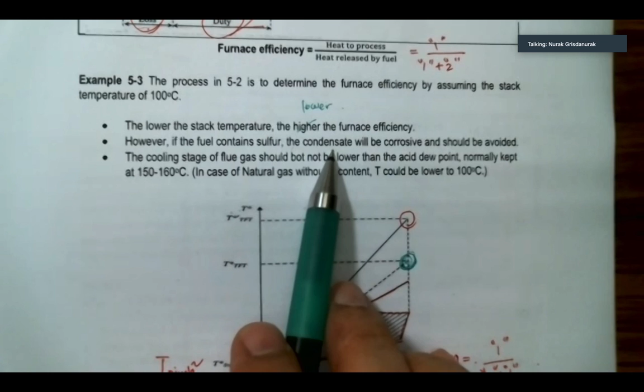Condensation occurs, and that is not good for the people living around the furnace and around the factory. So if your natural gas or fuel oil contains a lot of sulfur, you must think about the acid dew point. So what does it mean?